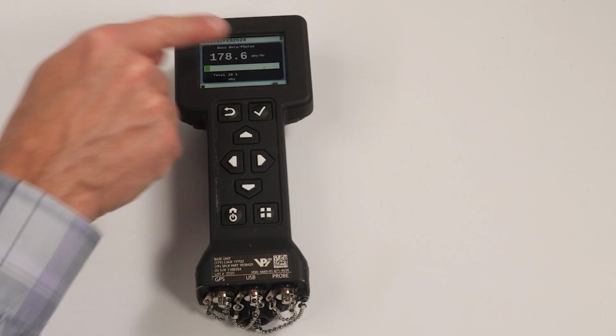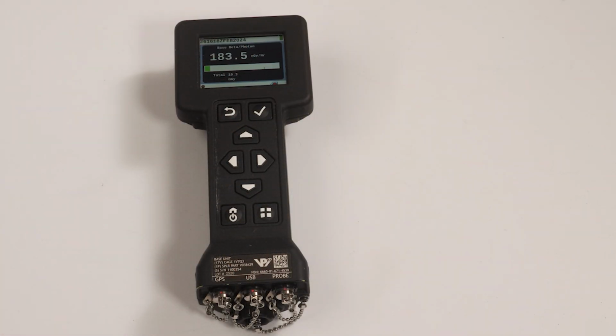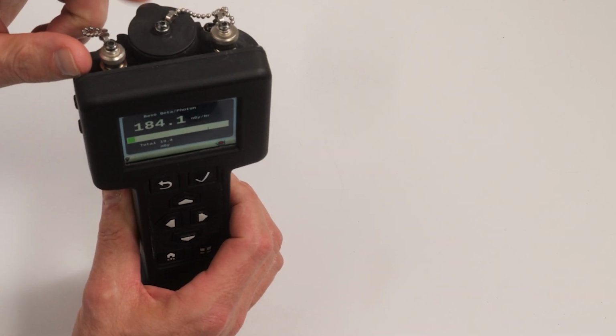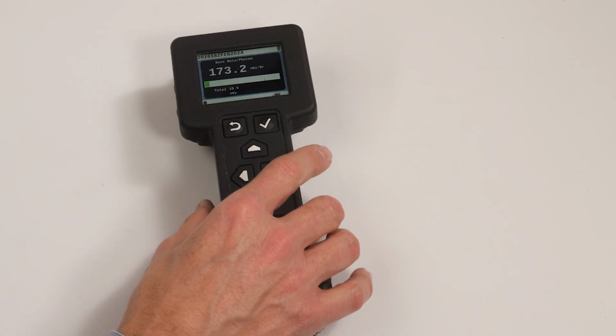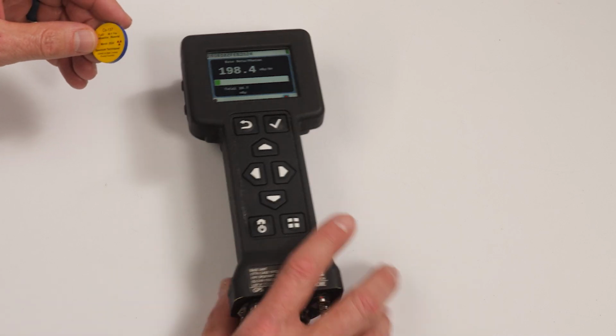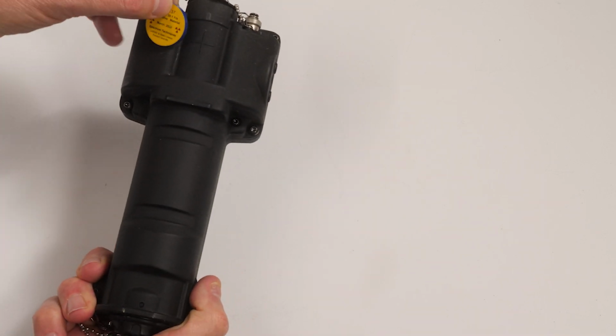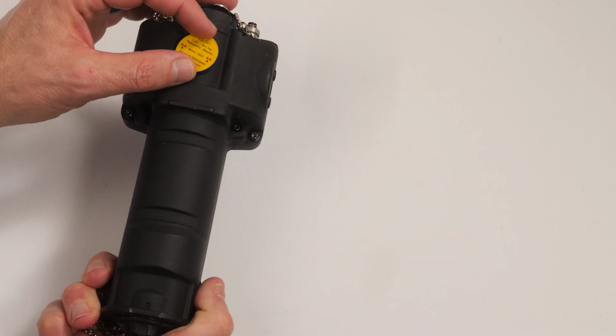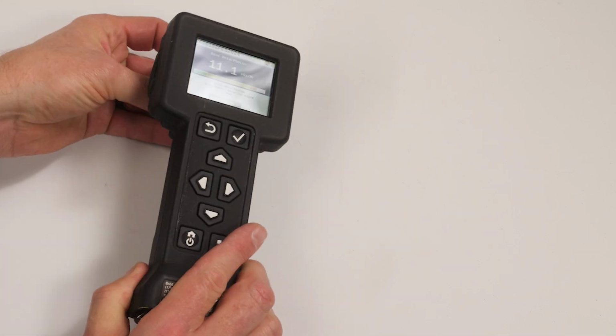The next thing to do is conduct a check on the radiation readings using the check source and following these steps. With this procedure, it is assumed that the base unit setting for radiation readings is set to display in grays per hour. First, ensure the beta window cap is installed. Locate the cesium-137 check source. Place the check source with the label facing away from the detector in direct contact with the base unit on the large crosshairs on the back of the base unit. This is the location of the low-dose GM tube detector.